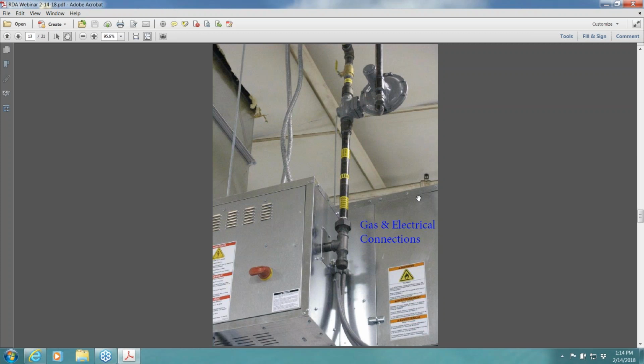And then you have your electrical connection. So the big thing on electrical is you need to know your phase and your voltage. Don't let a customer tell you he's got 220 volt. That's great, but that could be single phase, like what he's plugging his welder up to, or it could be 3-phase. Typical 3-phase runs from 208 to 230, and then you do have some industrial applications where you'll see a 440 to a 480. But your booth manufacturer will have to know what power is available. And then the contractor will have to take the manufacturer's information and let them know how many amps and what size breaker is required to be able to function and run the unit.